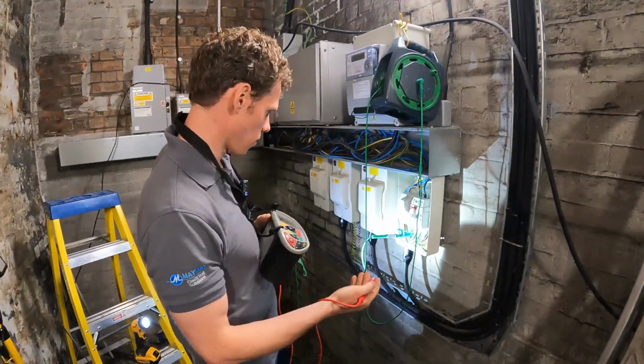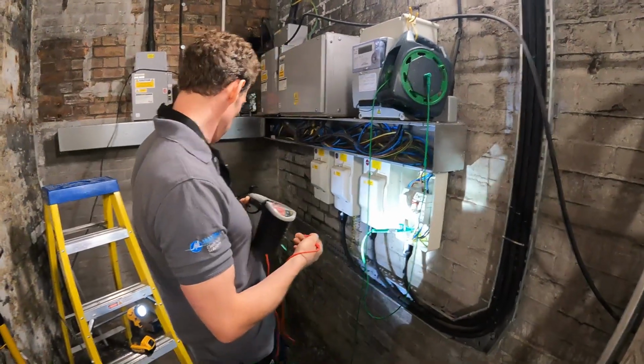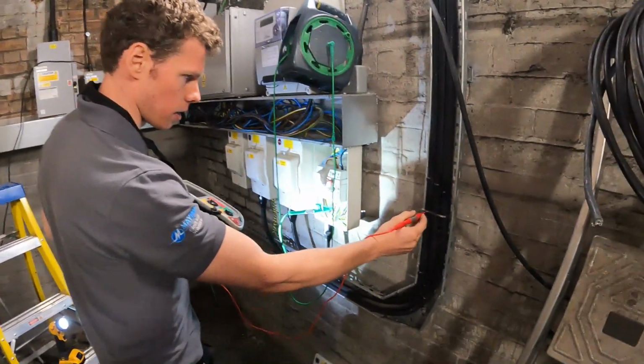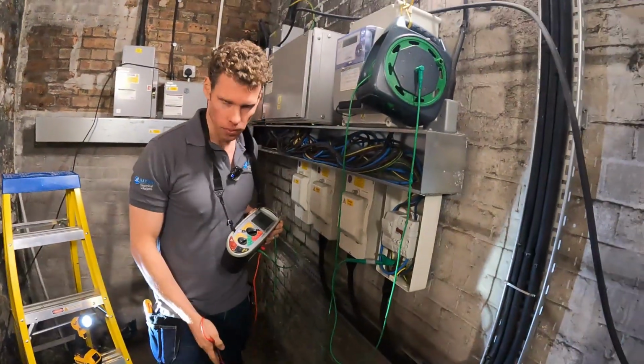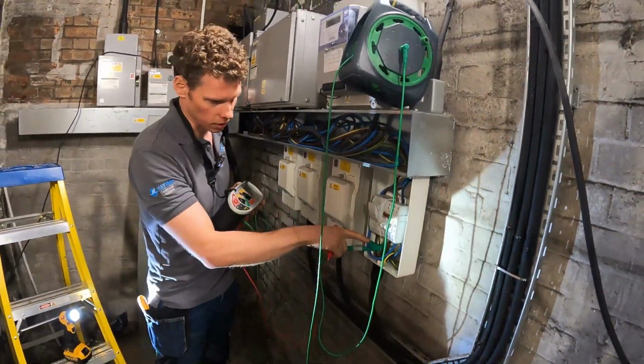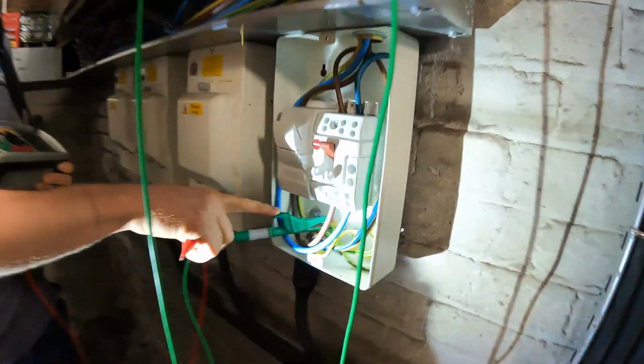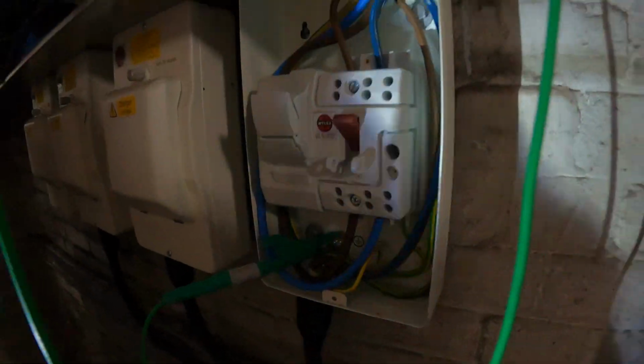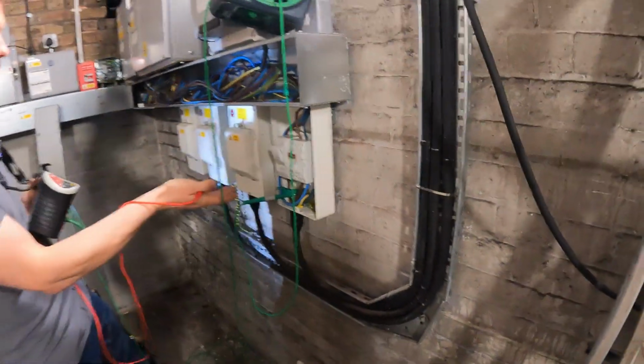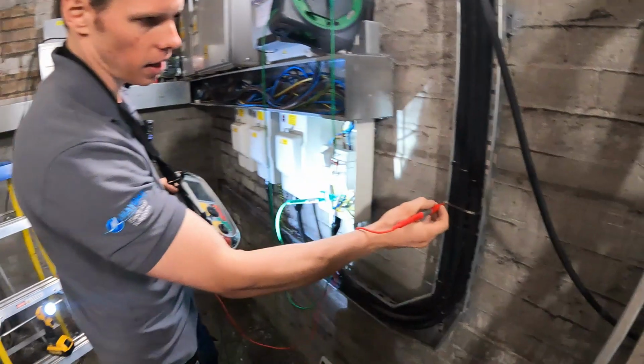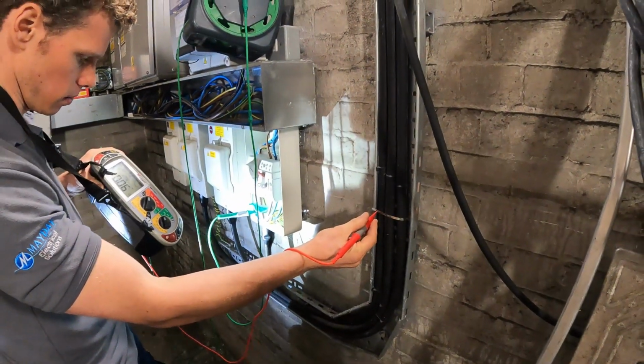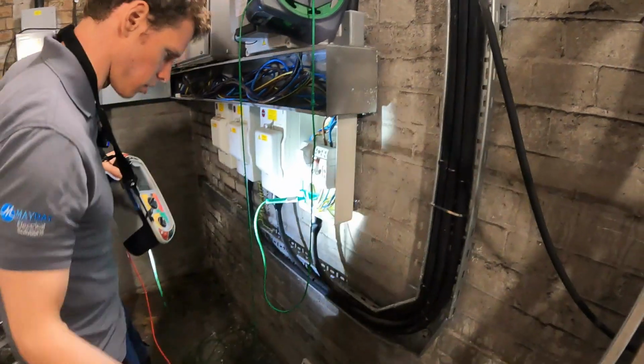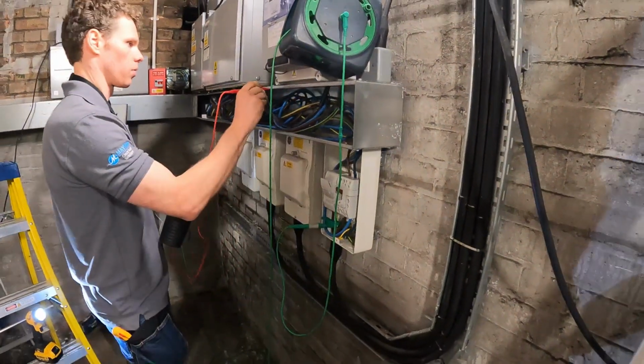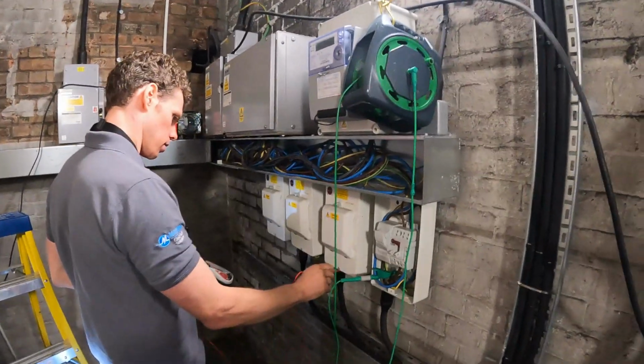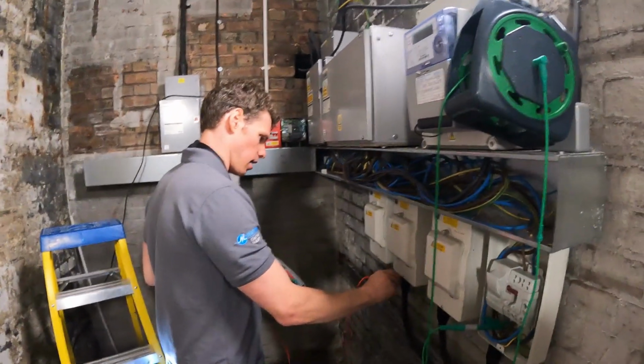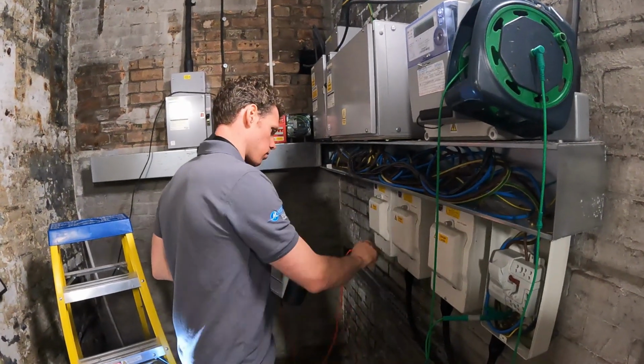This is the first bit of the installation here. So if we go along here, the other side of your R2 wandering lead connects onto the main earth terminal of the installation - well, this isn't the main earth terminal, but it's the easiest one to get to. If we go onto here, yeah, 0.01 ohms, very small amount. Just go onto our trunking here, into all our boxes - we can see immediately that everything is earthed, and it's just reassuring for us.